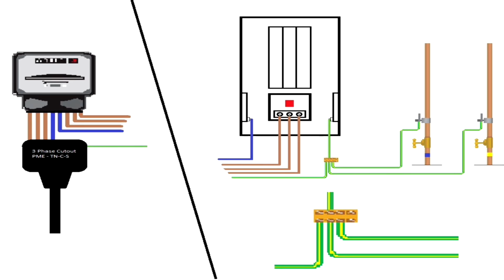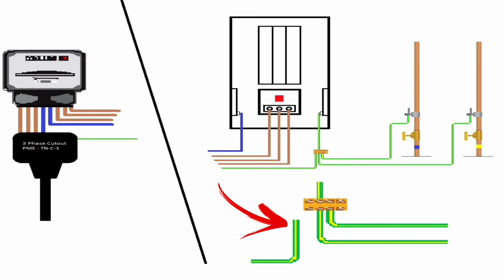So you have to remove those parallel earth paths for a true ZE reading. To do that, you disconnect the 16mm, whatever size it is, earthing conductor as I've shown there, which is the incoming one from the main supply. With that disconnected, remembering the board needs to be isolated, etc. before disconnecting it, we can now test from the disconnected earthing conductor, possibly 16mm or greater, to the board itself's individual lines to get our true external earth fault loop impedance. By removing it from the MET, you remove the parallel earth paths created by the metallic water, gas, structure of the building, etc. Let's see that test.